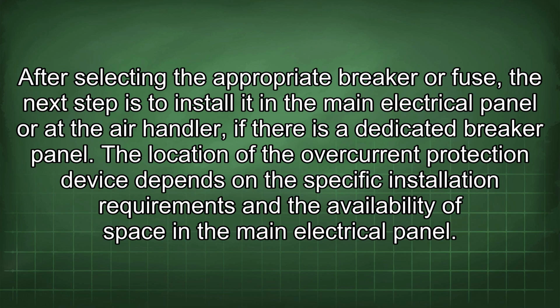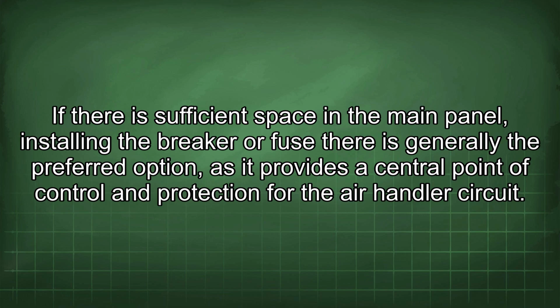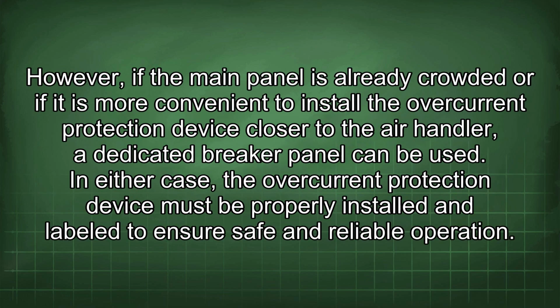After selecting the appropriate breaker or fuse, the next step is to install it in the main electrical panel or the air handler if there is a dedicated breaker panel. The location of the overcurrent protection device depends on the specific installation requirements and the availability of space in the main electrical panel. If there is sufficient space in the main panel, installing the breaker or fuse there is generally the preferred option, as it provides a central point of control and protection for the air handler circuit. However, if the main panel is already crowded or if it is more convenient to install the overcurrent protection device closer to the air handler, a dedicated breaker panel can be used. In either case, the overcurrent protection device must be properly installed and labeled to ensure safe and reliable operation.